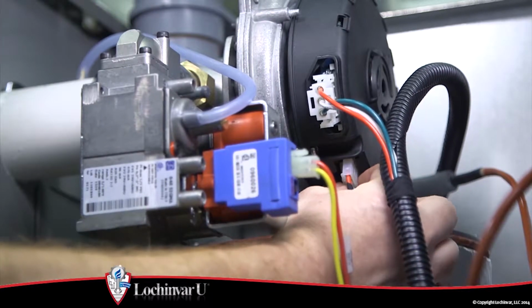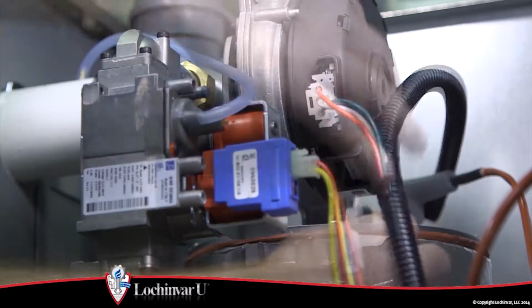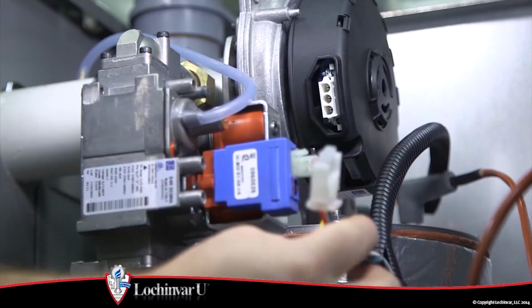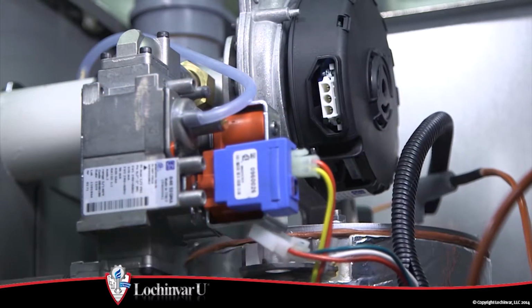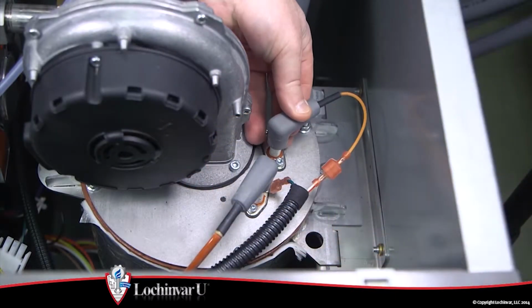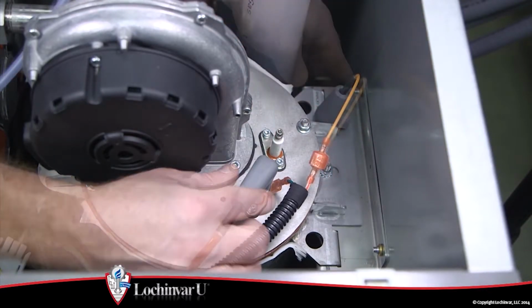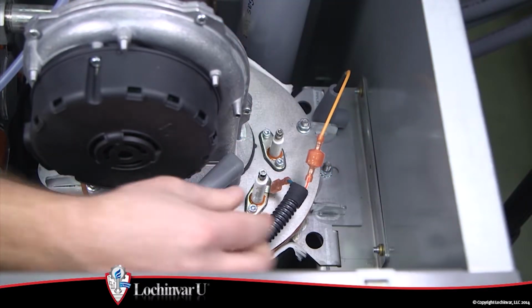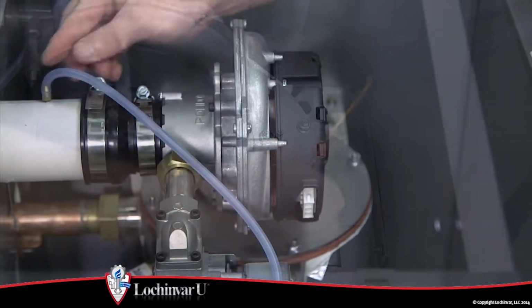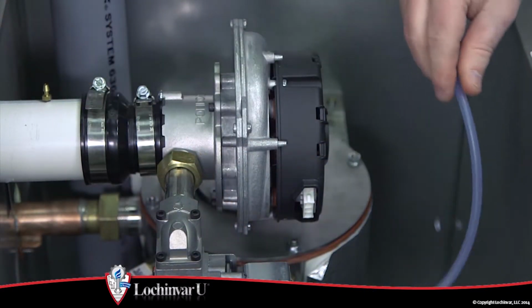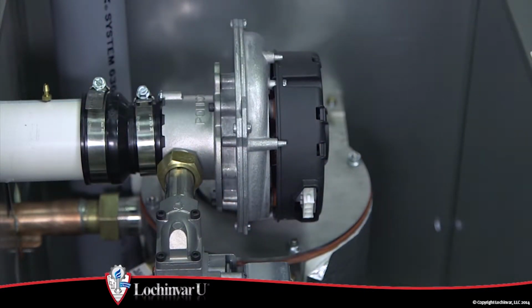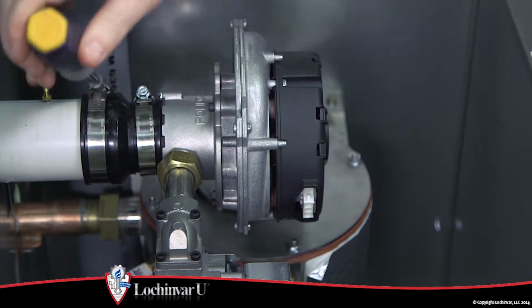Then locate and disconnect the 2 wiring harness connections on the combustion blower. Now remove the wiring from the flame rod, spark igniter, and ground terminals from the heat exchanger door. Next, remove the rubber hose from the air intake pipe, and loosen the band clamp securing the air inlet to the venturi.